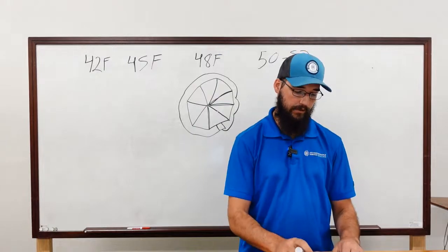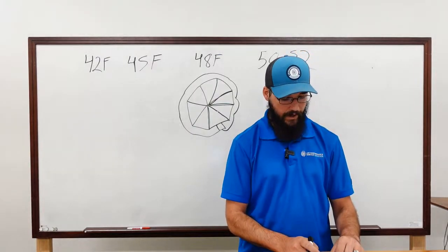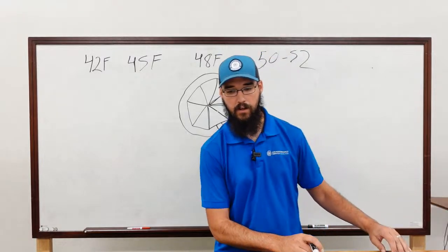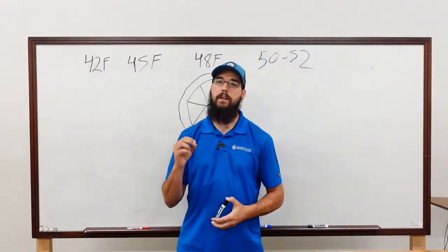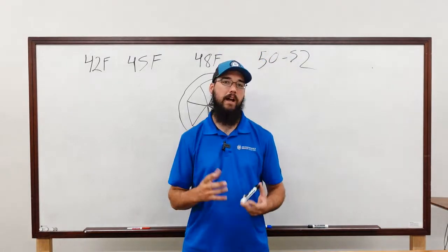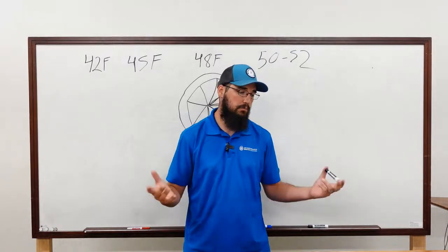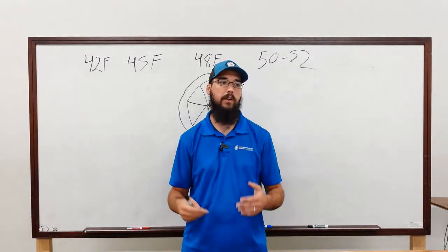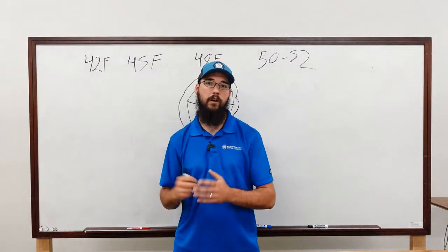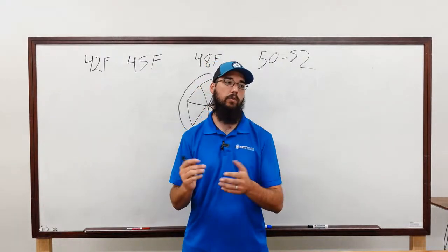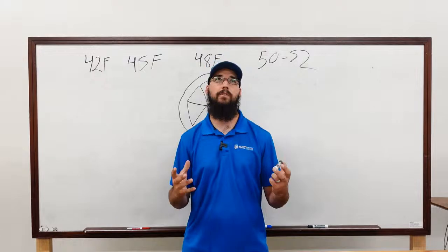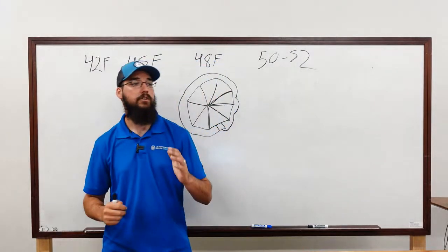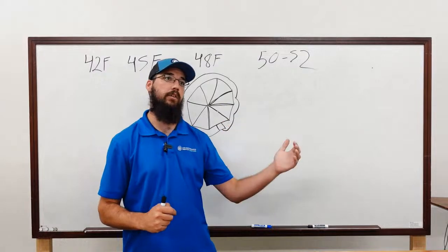In that scenario, the vast majority of centrifugals coming out today have some kind of variable speed control on them. Most specifically, they've got a VFD of some sort, whether it be an OEM direct, like York has their own, I think they technically go through a vendor. Anyway, York has their own drive. Trane uses a Danfoss variant.